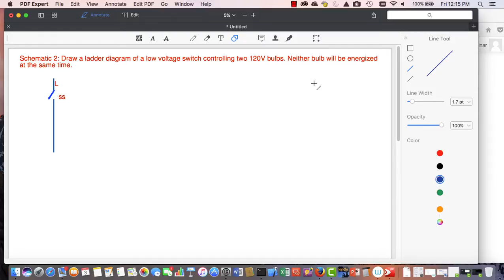Let's put our neutral in, because we know we have to have a neutral — we can't have a line without either a line 2 or a neutral. We'll bring them down to the same level. Now, we also know we need a control voltage side, or a low voltage side, so let's draw that line in. We haven't talked yet about how we'll create that low voltage, but that will come next.